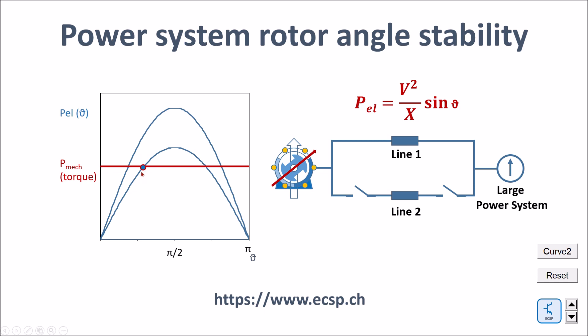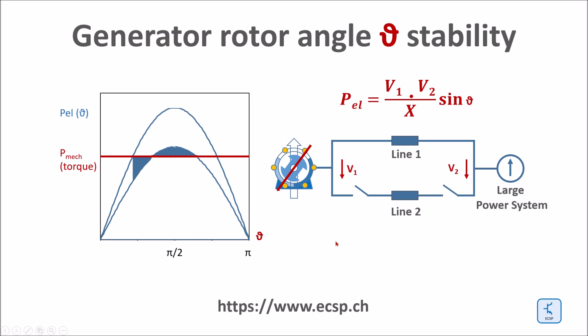The question is: can a new equilibrium be achieved, or does the generator exceed this no-return point? Let's see — this works. In reality there is a little more space because the generator is damped, so the oscillation is damped. There is a stability criterion: roughly, the surface of the deceleration phase above the mechanical torque line should be larger than the acceleration surface. If the deceleration area is larger than the acceleration area, the generator can be slowed down and stay synchronous. Otherwise, the acceleration phase puts more energy into the rotor rotation than can be taken out during braking, and the generator loses control.